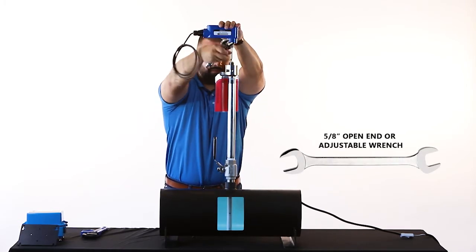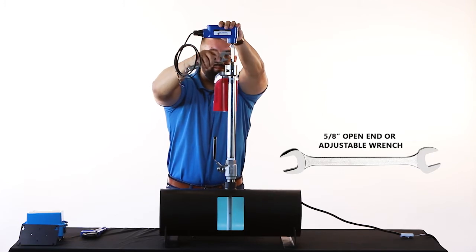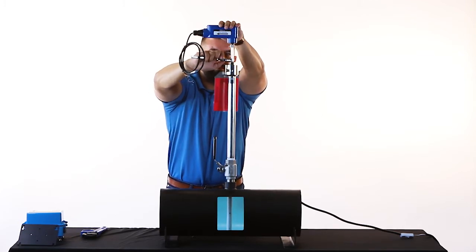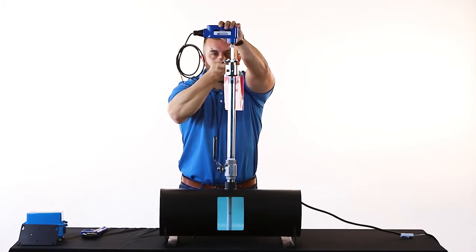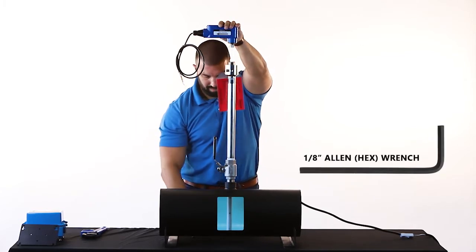Use a 5/8 open end wrench to tighten the stem locking collet nut while holding the flow sensor enclosure to maintain alignment with the pipe, and then use the 1/8 inch Allen wrench to tighten the preload fitting set screw.